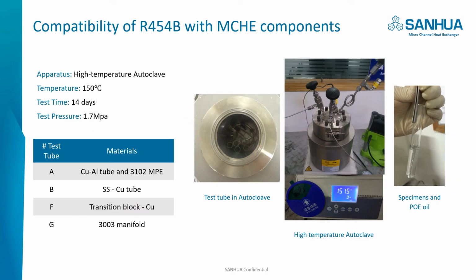Another question the industry cares about is how microchannel heat exchangers can be compatible with the low GWP refrigerant. So in SANHUA, we did compatibility testing with the quite popular refrigerant R454B. We used a high temperature autoclave to hold the specimens, and we set the temperature at 150 degrees C. The testing is under 1.7 megapascal for 14 days. There are 4 groups of materials. A is the copper aluminum tube and 3102 MPE tube. B is the stainless steel copper pipe. F is the transition block copper pipe. And G is the 3003 manifold.